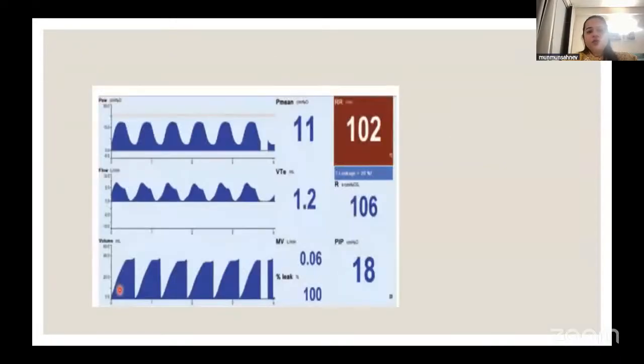So now again, we see the ventilator screen. And we see in this case, again, the pressures are being delivered. So the PIP is being reached, the PEEP is being maintained. Interestingly, now in the flow curves, we do not see the expiratory flow. And also in the volume curves, the volume which has been reached during the inspiration abruptly falls.